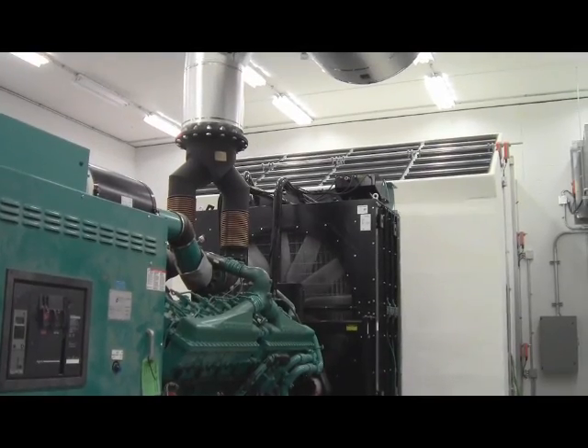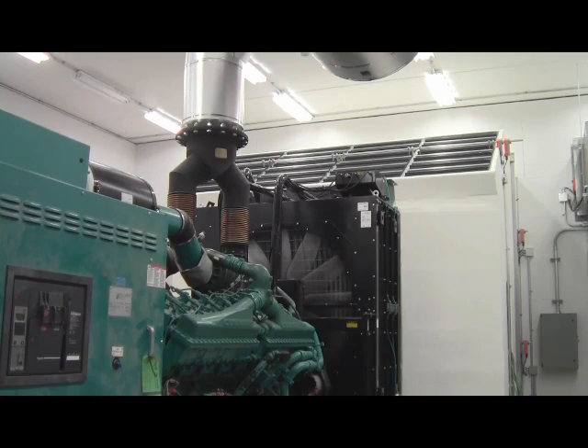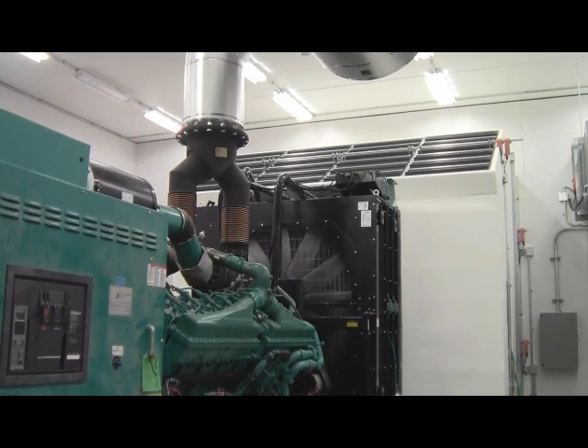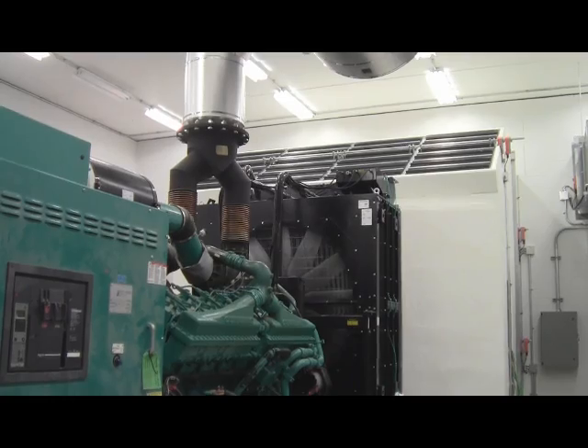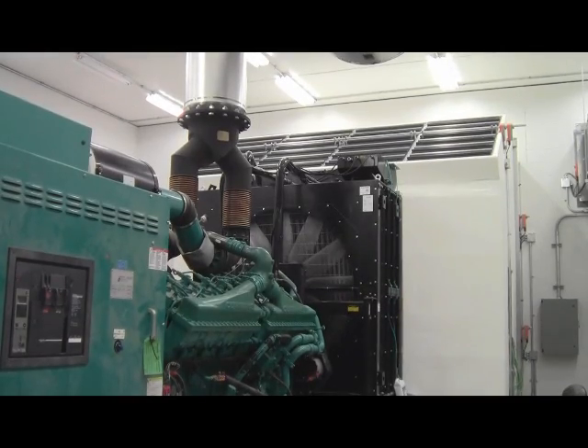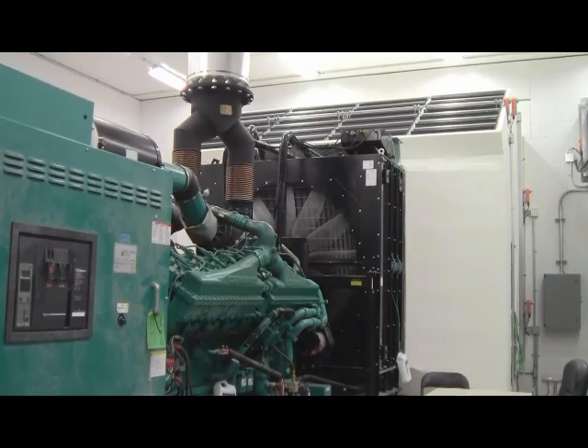The top louvers allow the air to circulate back in, to warm up the building and help warm up the generator from the initial start. As it starts heating up inside here, the top louvers will close, and the louvers that are to the outside on the wall will open, and the hot air will exhaust out through there. It will regulate, like I say, with the internal thermostat.